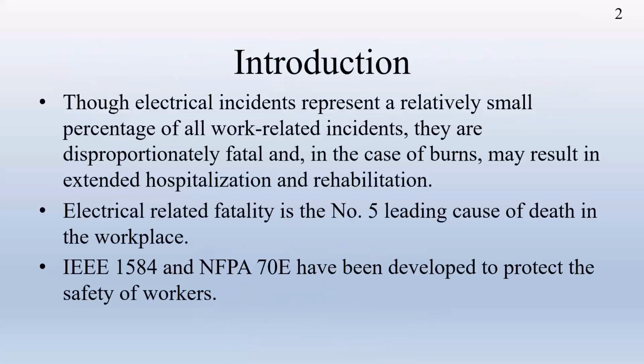As we know, electrical incidents represent a relatively small percentage of work-related incidents. However, they are disproportionately fatal, and in the case of burns, may result in extended hospitalization and rehabilitation. According to Richter, electrical-related fatality is the number 5 leading cause of death in the workplace. And from the arc flash point of view, IEEE 1584 and NFPA 70E have been developed to protect the safety of workers.